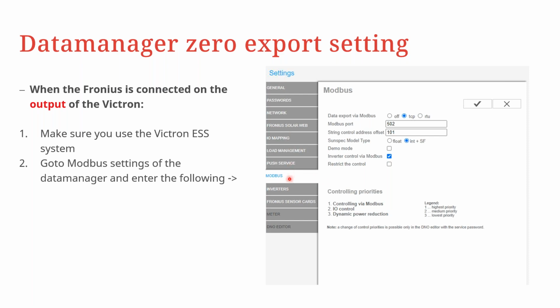you go to Settings, then Modbus, and at Modbus you enter exactly what is shown here. For data export via Modbus, you select TCP, and then the Modbus port is 502, the string control address offset is 101, and the SunSpec type model is integer plus SF. You also have to tick that you control the inverter via Modbus. When it comes to the control priorities, make sure that Modbus has been given the highest control priority. Once you are done with this, click on the Save button.